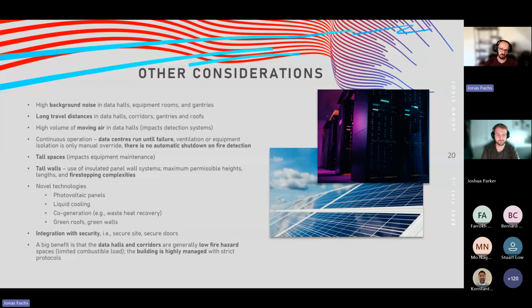There are tall spaces where the data halls are often 6, 7, 8 meters tall, which impacts your equipment maintenance, your equipment positioning. Also, in turn, it introduces tall walls into the buildings, and often you will see systems using insulated wall panel systems, which then in turn impacts your material specifications, your maximum permissible heights, lengths, and obviously fire stopping as well, because insulated wall panels, they are a separate category under the EN requirements of fire stopping. You cannot assume that your concrete tested fire stop will perform in insulated wall panel, or that your plasterboard fire stop will perform in an insulated wall panel. They are entirely separate system categories. There's no cross-pollination right now with regards to the field of application.